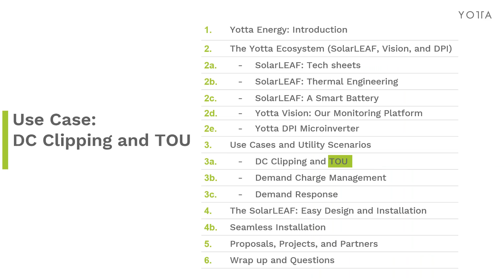Time of use, same thing here. You're seeing the time-of-use chart. This is normal production, and what we're doing is shifting it: capturing it here and using it later in the day at a certain time. The nice thing about the time-of-use system is it can be programmed by you, the user, via your computer, handheld phone, or an app. You can discharge at a certain time, at a certain rate, for a certain period of time. Those are the three variables you can set.